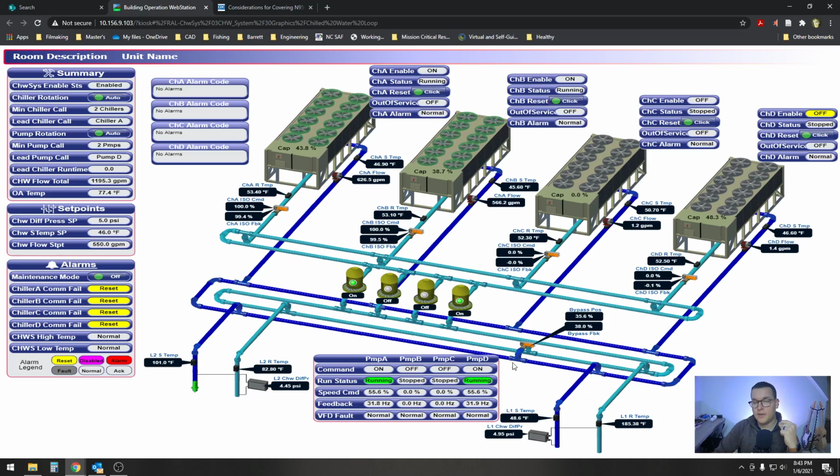Literally the only thing that controls the pump speed is these 2 differential pressure sensors. These sensors' jobs are only to control the pump speed, and the byproduct of that is the amount of water flowing through the system as a whole. If you watch it, again, the lower the differential pressure, the higher the pump speed. We just watched it happen again.